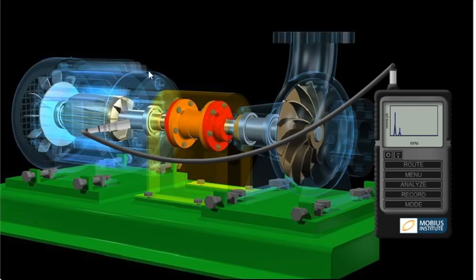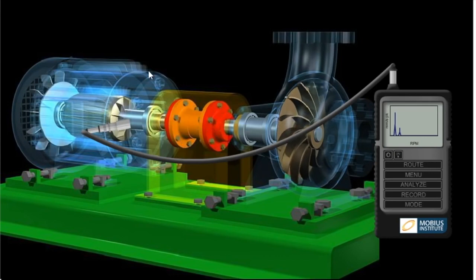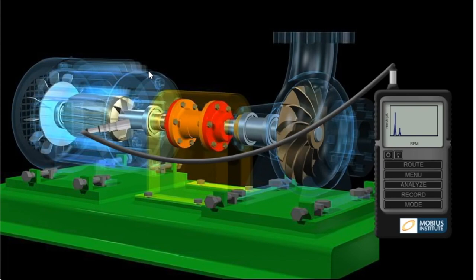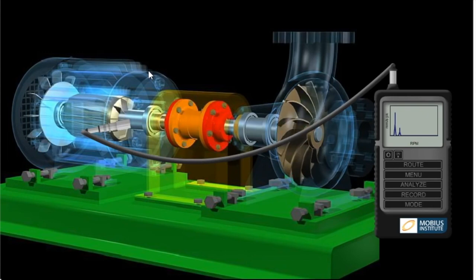Whether it's vertical or horizontal, those two positions tell us about radial vibration, vibration radiating out. So if there was misalignment and offset or parallel misalignment or unbalance, we get a lot of that sort of up and down and side to side motion.